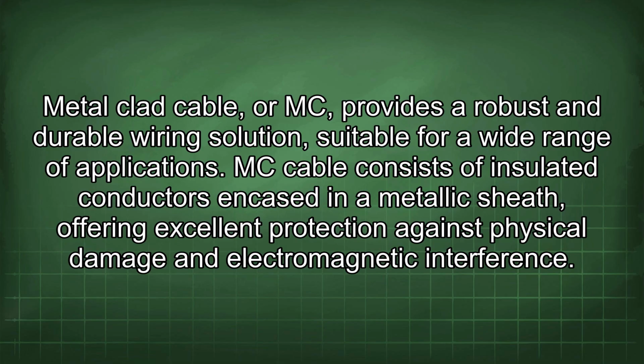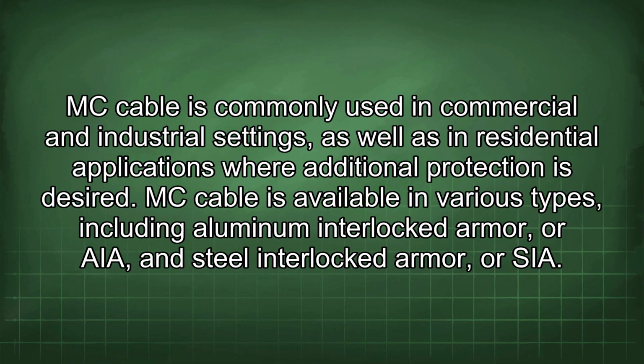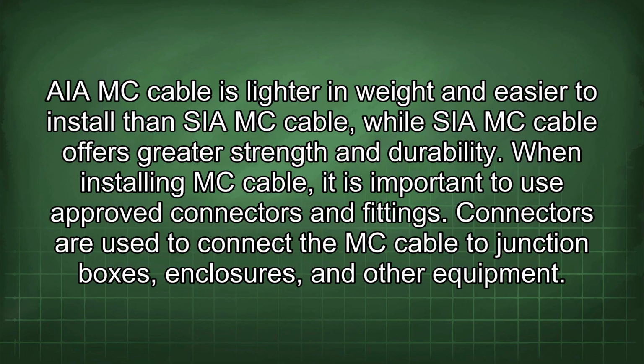Metal-clad cable, or MC, provides a robust and durable wiring solution, suitable for a wide range of applications. MC cable consists of insulated conductors encased in a metallic sheath, offering excellent protection against physical damage and electromagnetic interference. MC cable is commonly used in commercial and industrial settings, as well as in residential applications where additional protection is desired. MC cable is available in various types, including aluminum interlocked armor, or AIA, and steel interlocked armor, or SIA. AIA-MC cable is lighter in weight and easier to install than SIA-MC cable, while SIA-MC cable offers greater strength and durability.